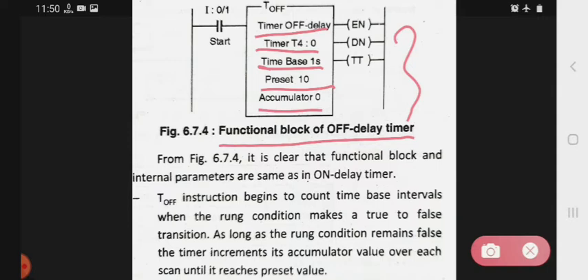Now let's see what happens in the off delay timer. We have the functional diagram. First, the TOF instruction begins to count time-based intervals when the rung condition makes a transition from true to false. That is, whenever the rung condition in the PLC transitions from true to false, the TOF instruction will start counting.